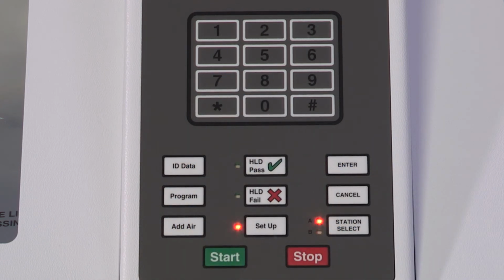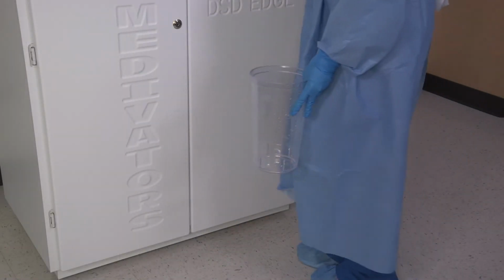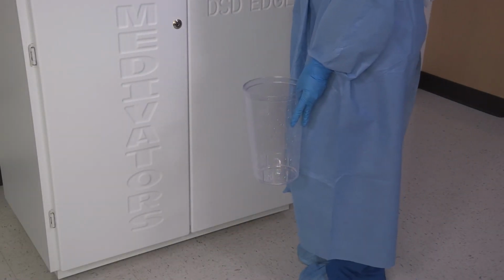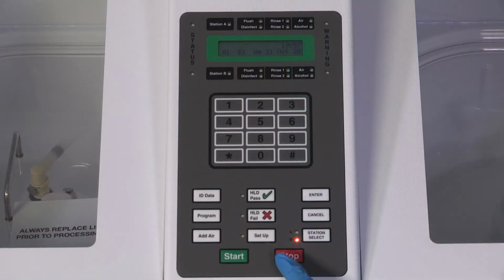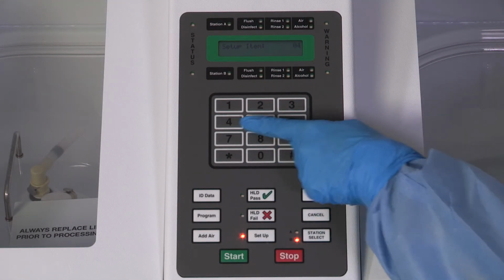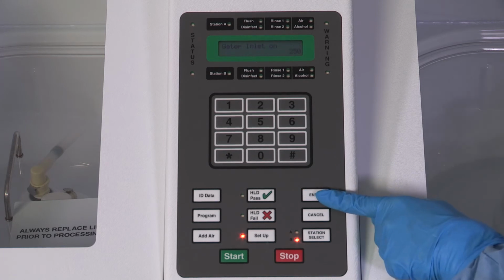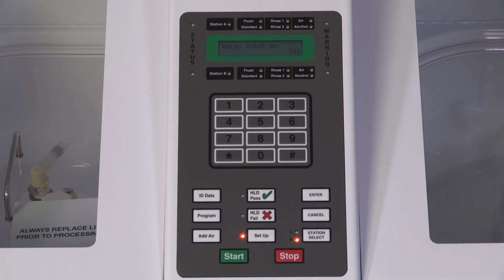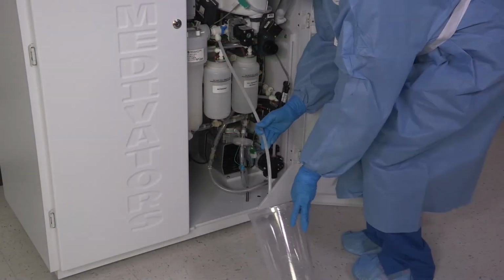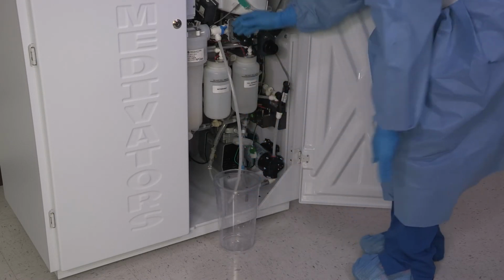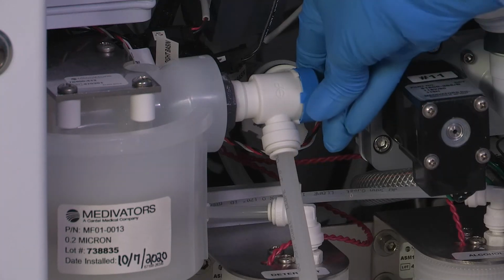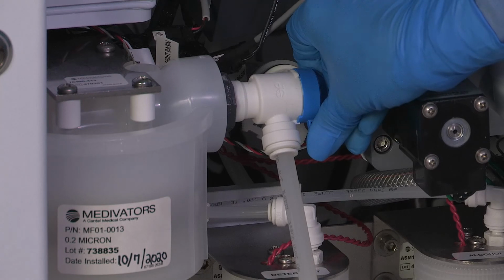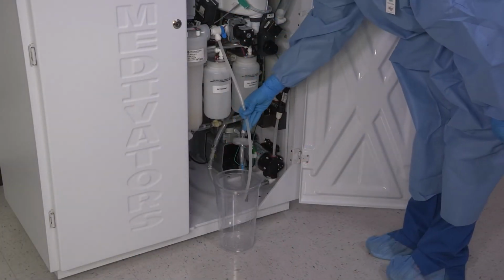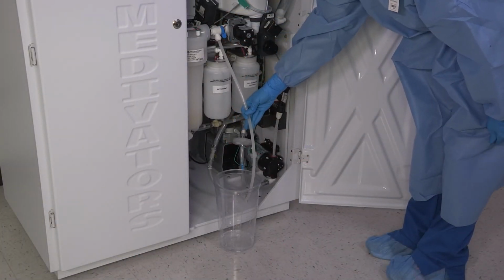Once the waterline disinfection completes, air must be purged from the internal filters. A container that holds at least 1 liter of liquid is needed. Press Setup, 43, Enter, to open the incoming water supply valve and provide water to the internal filter. Direct the purge line from the internal filter housing into the container. Slowly open the air bleed valve until the air is purged from the filter housing and a steady stream of water flows from the purge line.